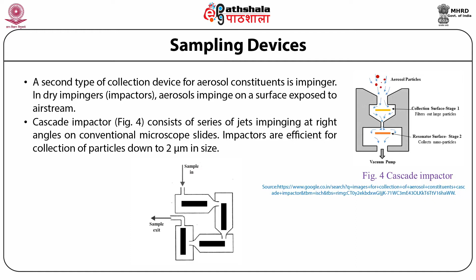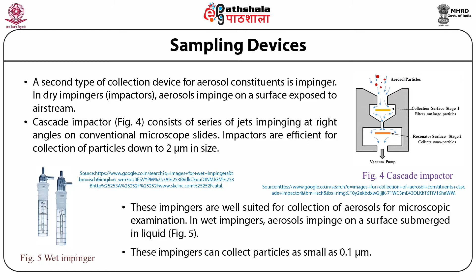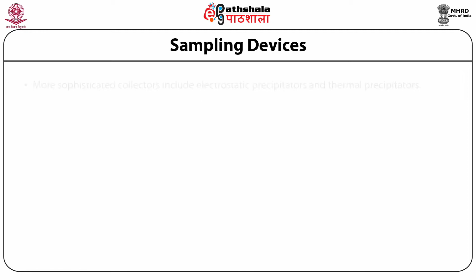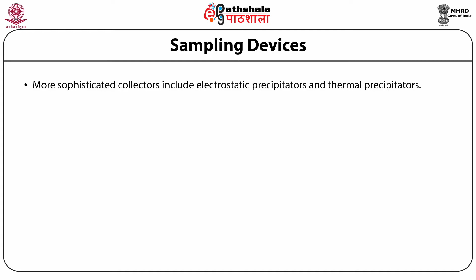In wet impingers, the aerosol impinges on a surface submerged in a liquid. A glass tube with an orifice at the end is directed towards a flat surface, which can be the bottom of the collection vessel or a glass platform connected to the tube. The particles are retained by the liquid in the collection tube. The liquid should not be a solvent for the particles to be collected. These impingers can collect particles as small as 0.1 micrometer. More sophisticated collectors include electrostatic precipitators and thermal precipitators, which will collect particles down to 0.001 to 0.01 micrometer.